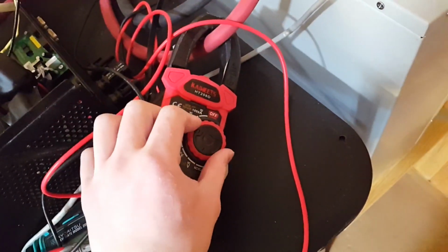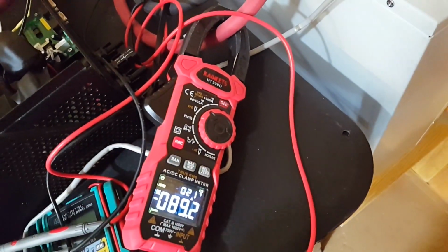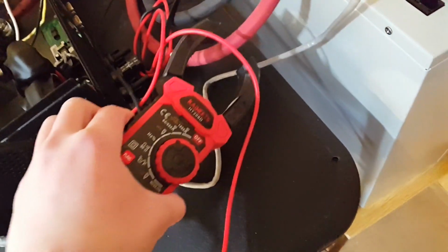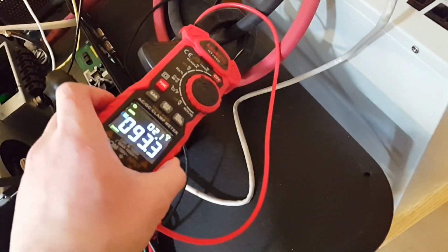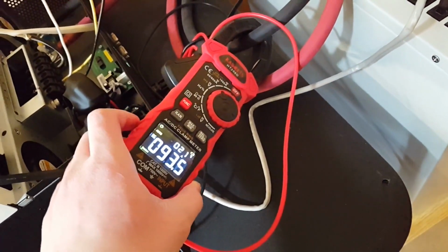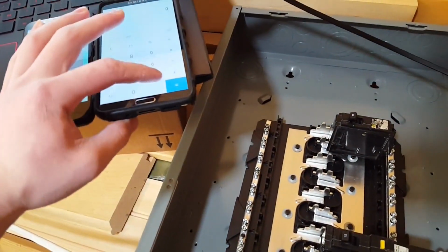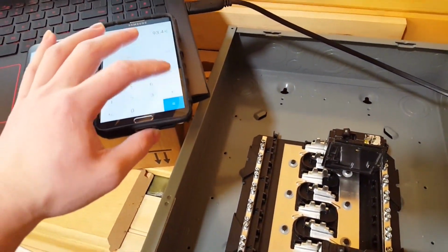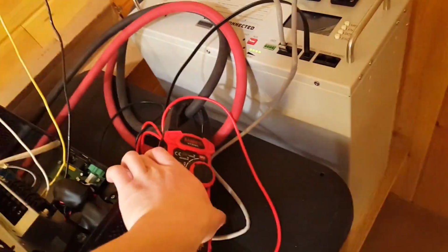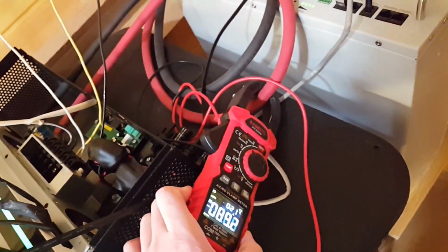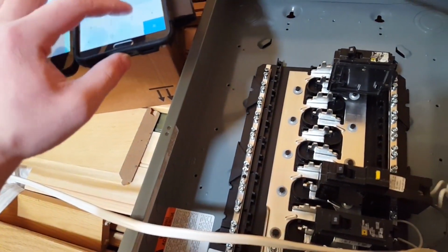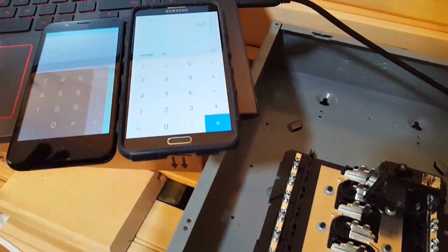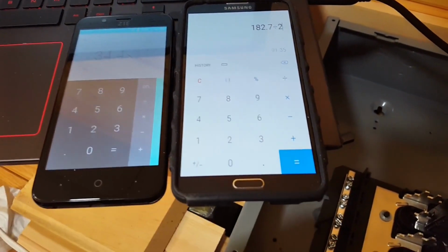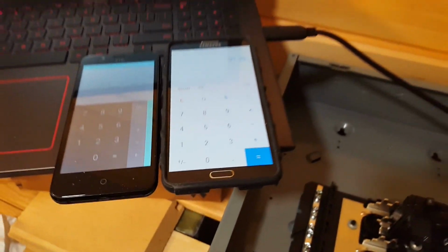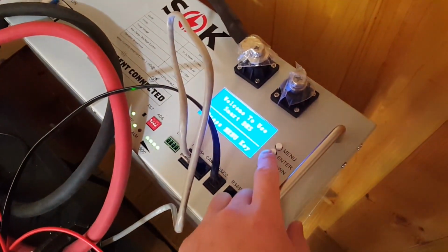DC amps. Oopsie. One cable is 89.3. The second cable is showing 93.4. So let's average that. 93.4 plus 89.3 equals 182.7. Divide that by 2. So it's an average of 91 amps. Let's look at the BMS status before it shuts off again.